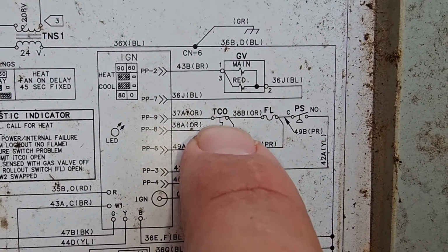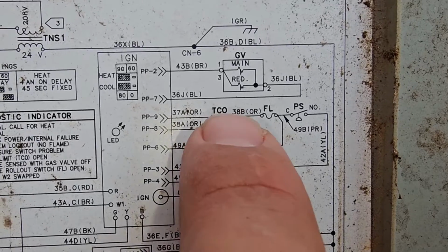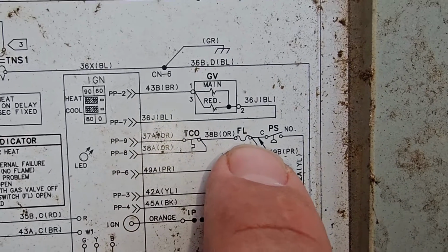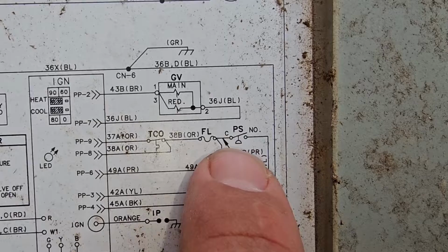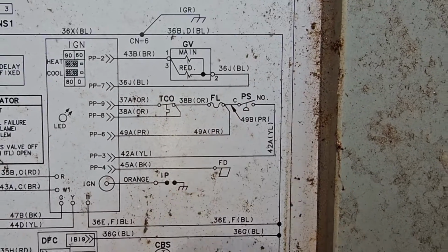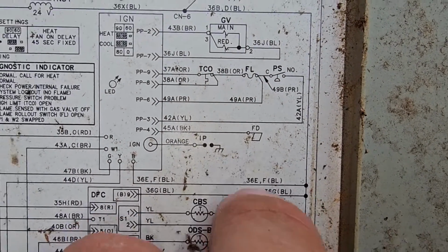It says right here, TCO, temperature limit switch. FL, fusible link, that's the rollout switch. And then PS, pressure switch. So I just want to show you that, and show you a little bit more of the schematic here.